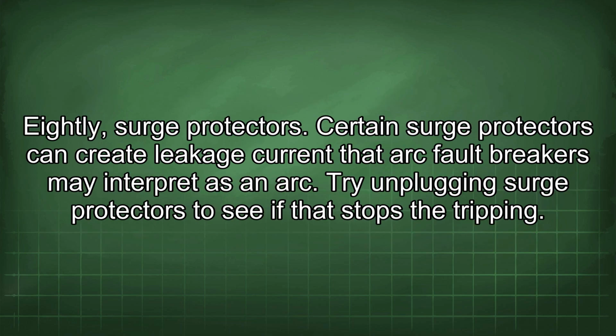Eighthly, surge protectors. Certain surge protectors can create leakage current that arc fault breakers may interpret as an arc. Try unplugging surge protectors to see if that stops the tripping.